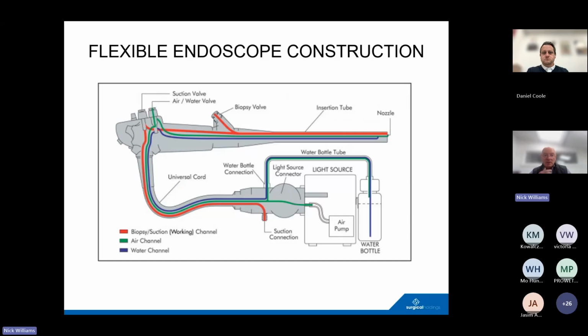To look at the channels in a little bit more detail, this is obviously a diagrammatic. You wouldn't get a scope that short, but this gives you an example of an illustration of, for example, the biopsy suction channel here, the way it goes, the air water channels, and they often join just here before the connection through right to the light source, the water bottles, the air pump, and the suction connection. All of these obviously have to be cleaned, disinfected, and lumens, as I'm sure you know, aren't the easiest of things to clean and disinfect.